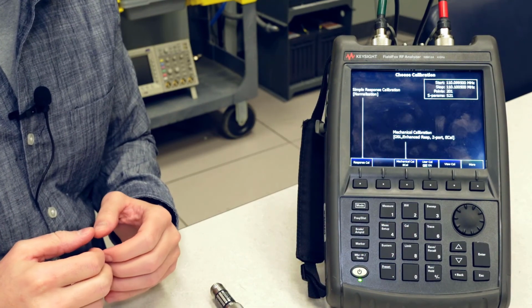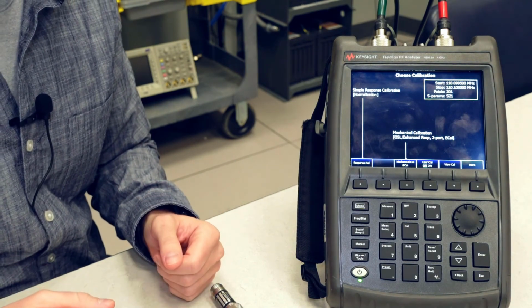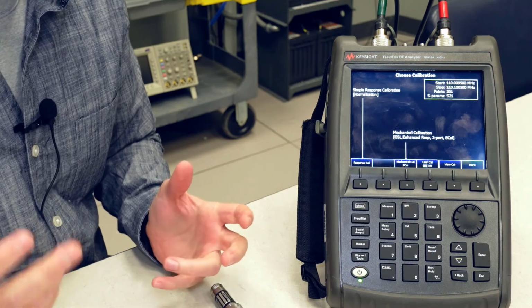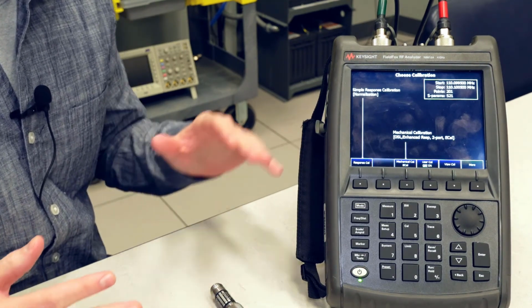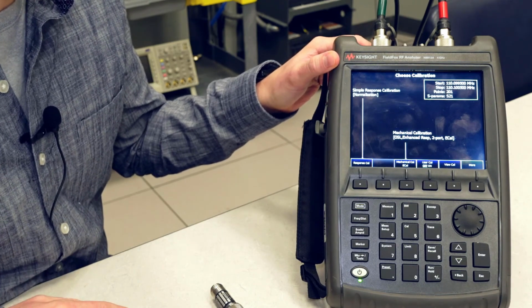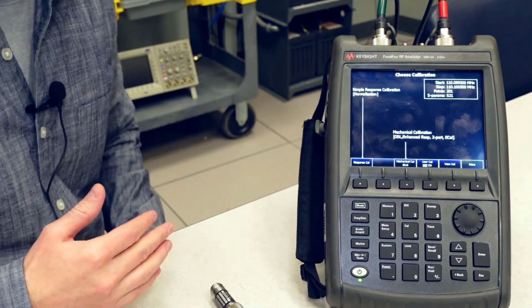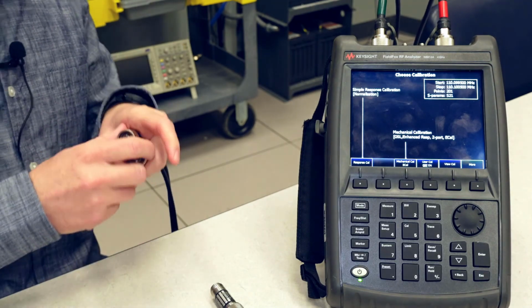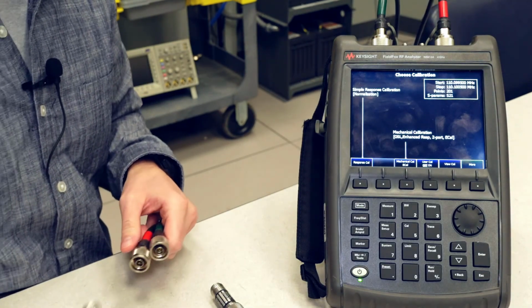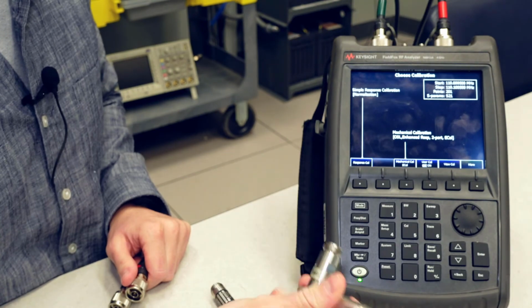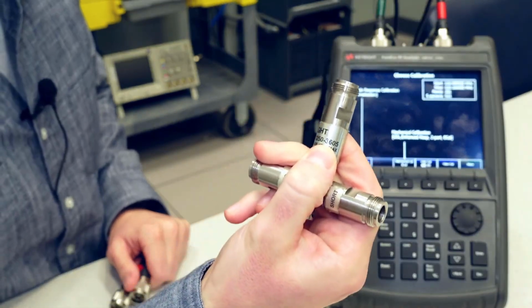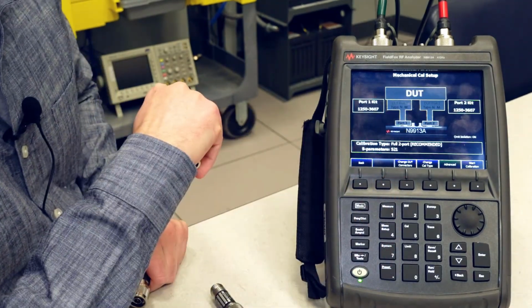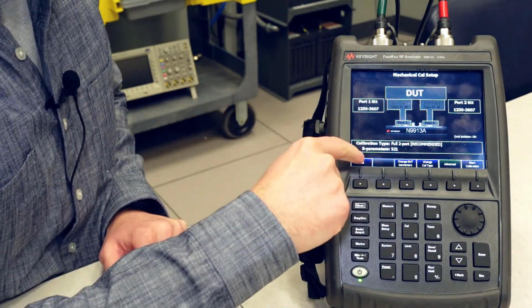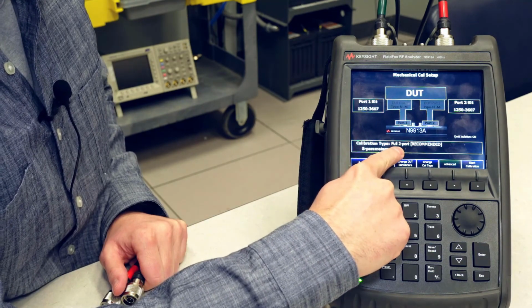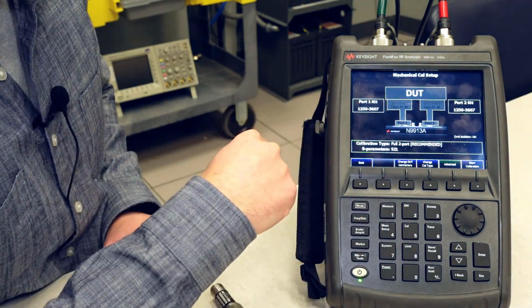And calibration is important to perform every time we start up our FieldFox for the first time. There are well-defined and understood systematic errors that are measured and calculated during the calibration process. And so when we perform this calibration, it removes those from any subsequent measurements. You should have with you the calibration-T accessory, and the part number of mine is the 3605. On the FieldFox, when we hit mechanical calibration to bring up this process, it's already recommending that we do a full 2-port calibration based on our S21 settings.